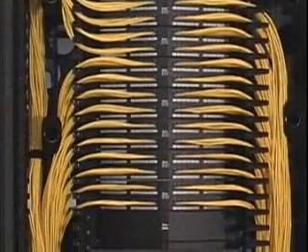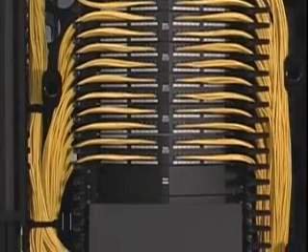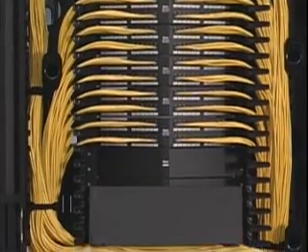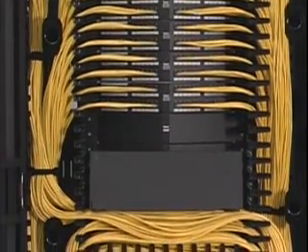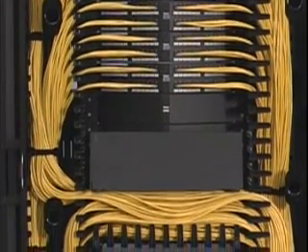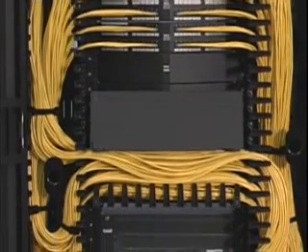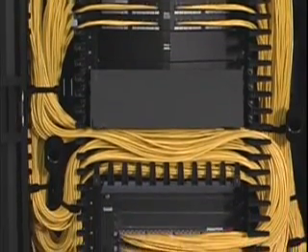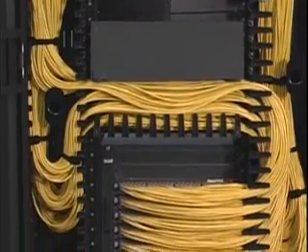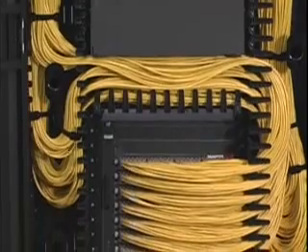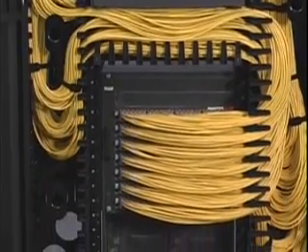Port assignment should be done so that the patch cords routing from the left side of the switch correspond with the left half of the patch panels. Patch cords routing from the right side of the switch correspond with the right half of the patch panels.